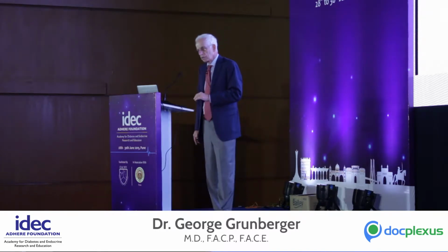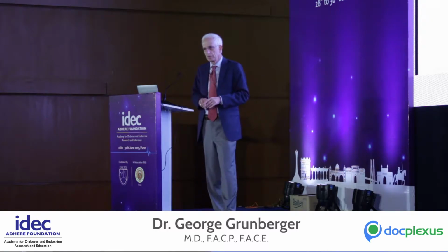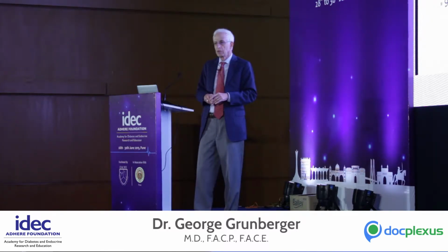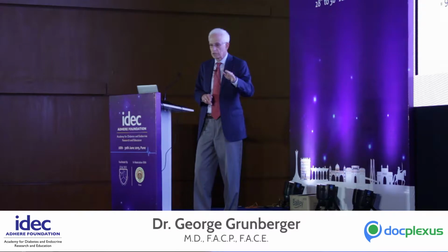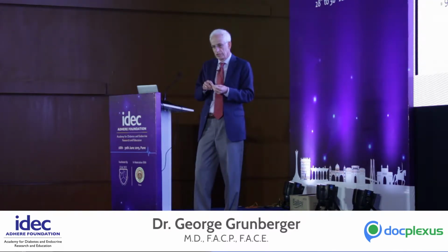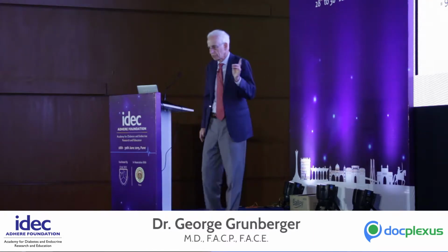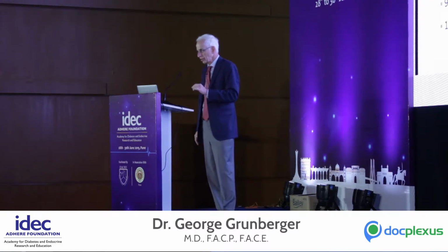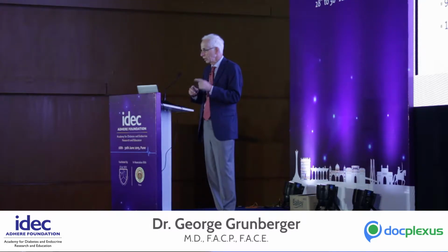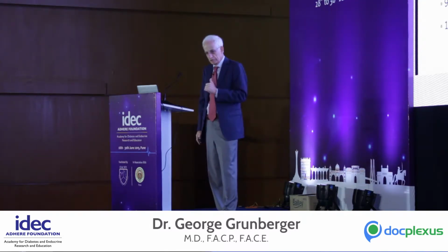And the performance, okay, how does it compare? Remember, I said MARD under 10% is approved to be used without finger sticks. If you do 3 to 4 calibrations with finger stick each day, the MARD is less than 10%. If you do 2 calibrations a day, patients still have to calibrate with finger sticks to make sure that's okay, and it's a little bit above 10%. Okay, so this is the Medtronic performance.